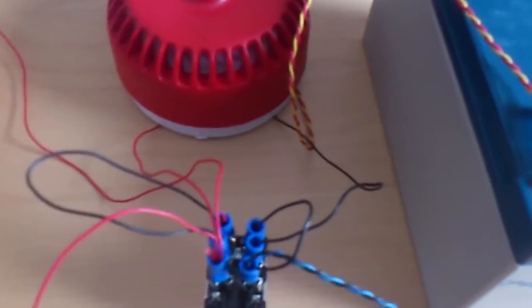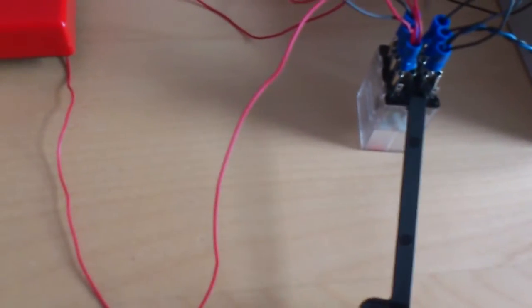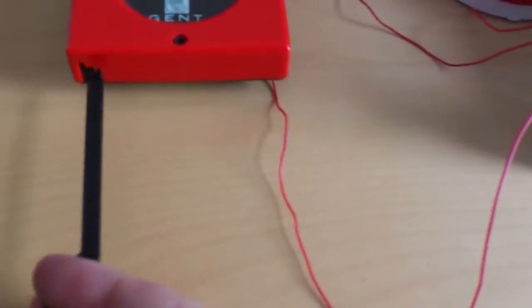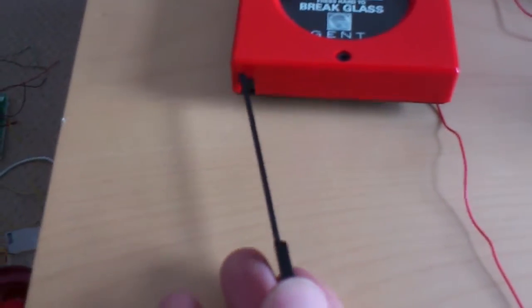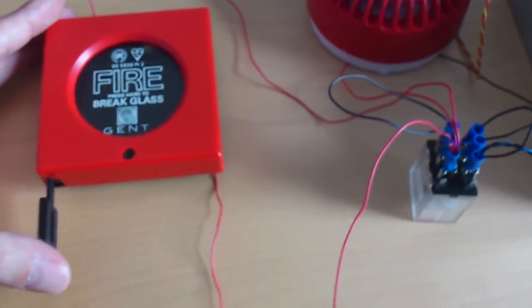So I'll explain exactly what you need to do after I've given a quick demonstration, which of course would be necessary. So what we're going to do, we're going to simulate breaking the call point by using the test key. So the test key itself is going to activate the call point, which will then activate the relay, and then I will show you what happens when we reset the call point. So first of all, we'll put the test key into the call point. So we're going to activate the system as such, so here goes.